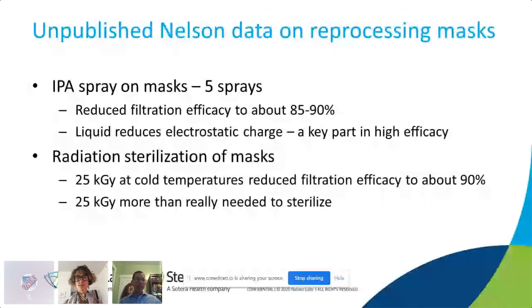The issue, and this is something I did not know because masks have not been my specialty in the past, is that the N95 rating, that extra bump up to N95, is usually based on the electrostatic charge that the mask material has. And as you reprocess those, mainly when it hits liquids, that will reduce or eliminate that electrostatic charge. Then you only have the material itself causing the filtration efficacy. So that does eliminate quite a few sterilization methods that use very high humidity or actual moisture, because it makes it harder to still obtain good data on the masks afterwards.